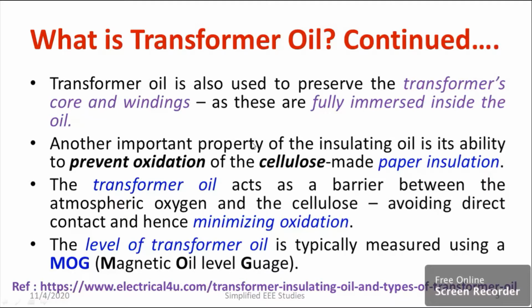Another important property of insulating oil is its ability to prevent oxidation. The transformer uses cellulose material, which helps prevent oxidation. The transformer oil acts as a barrier between atmospheric oxygen and the cellulose, avoiding direct contact and minimizing oxidation. Basically, it prevents oxidation - that is another specialty.